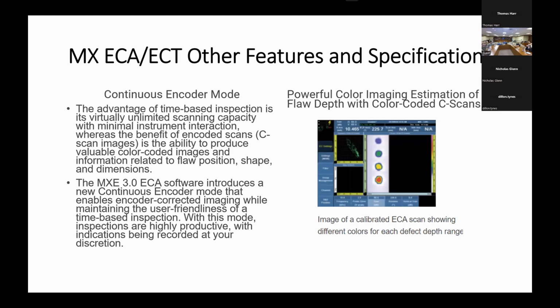Some other features and specifications for the MX ECA. So we have continuous encoder mode. The advantage of time-based inspection is virtually unlimited scanning capacity with minimal instrument interaction. It has the ability to produce valuable color-coded images and information related to flaw position, shape, and dimensions. We also have powerful color imaging estimation of flaw depth with color-coded C-scan. This picture that I have up here has 4 indications on a test sample, and they're all different colors, which correlate with the depth of those indications. That's awesome.